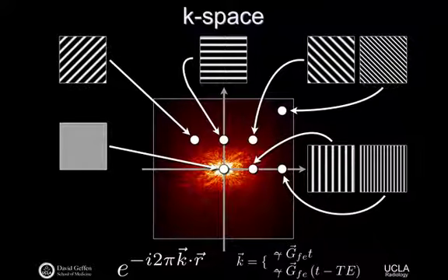This is the spatial frequency encoding term, right? This is the magic to how we could possibly do spatial frequency encoding. Each one of these is potentially a function. It depends on K, right? K depends on what's the applied gradient at a particular point in time and how long it's been applied for. And then it's mapped over all points in space. So what we were interested in doing is estimating our S of k's, right? If we can sample all of our S of k's, fill up k-space, then we're one step, a Fourier transform, away from having the image.